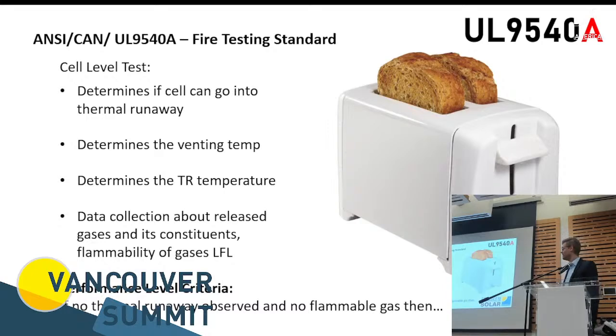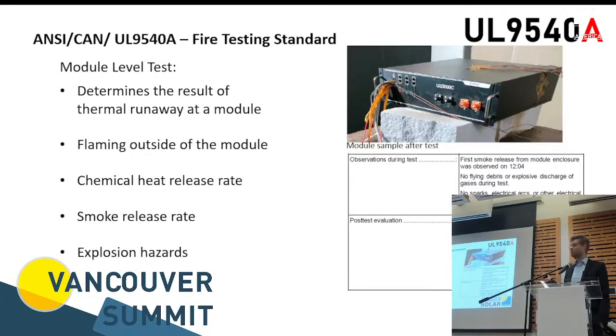So most manufacturers have to go to the next level, which is the module level test. So now you put multiple of those cells that could have a thermal runaway in an enclosure or a module. That can be a 19-inch module, like multiple manufacturers, or it can be a different enclosure, like a stacked battery system with the enclosure already tied into it. And then the whole thing starts again. The lab tests, okay, when is it going into a thermal runaway?